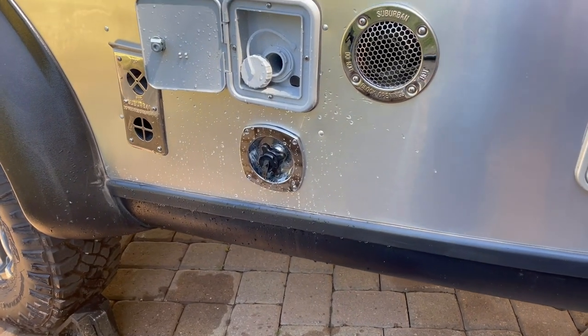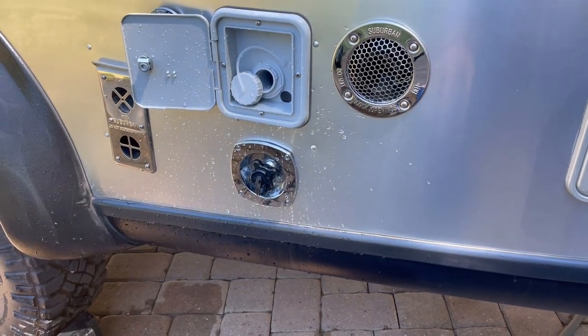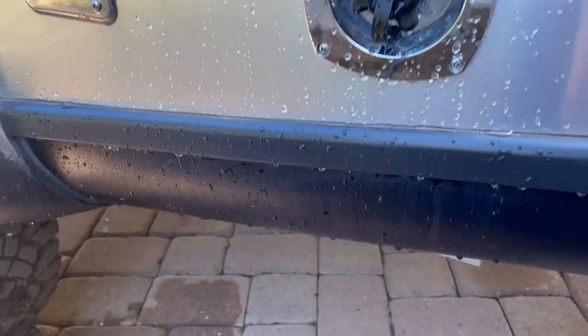Okay, so next step. We filled up the tank with the sanitized solution, let it sit for a little over 24 hours, and ran some water through the lines inside to get them sanitized as well as the tank. The next step is to drain the tank. I've opened up the line to make sure it was topped off since I did put a little extra water in through the lines.